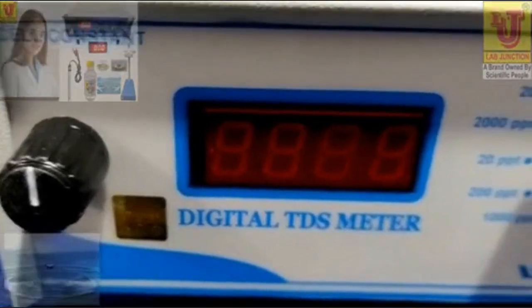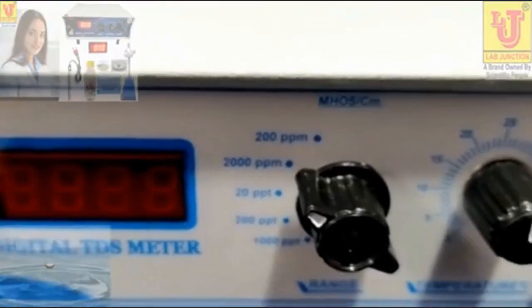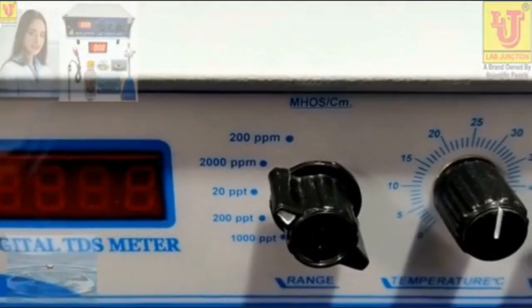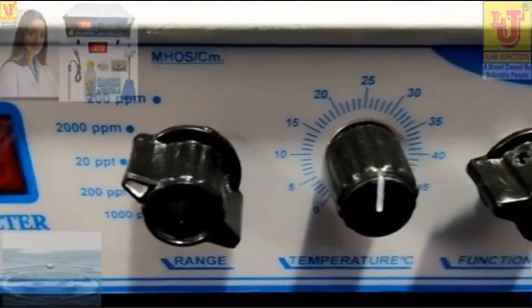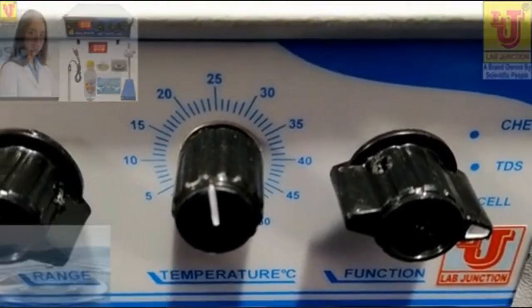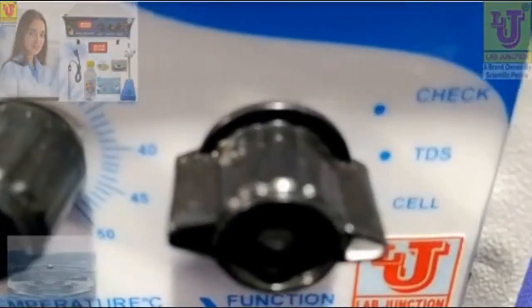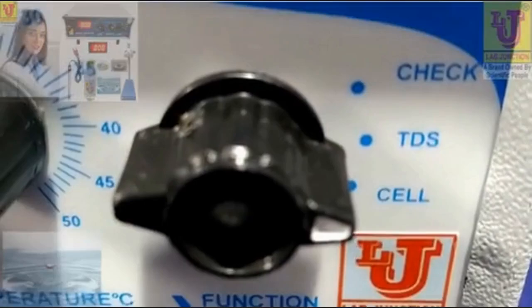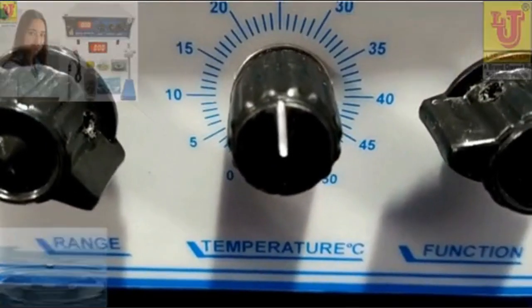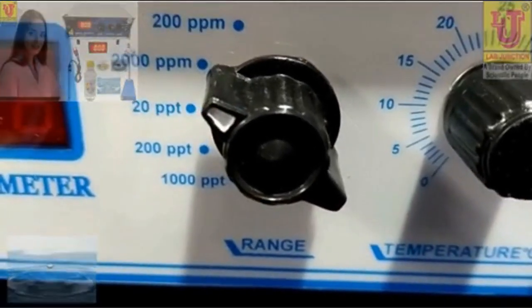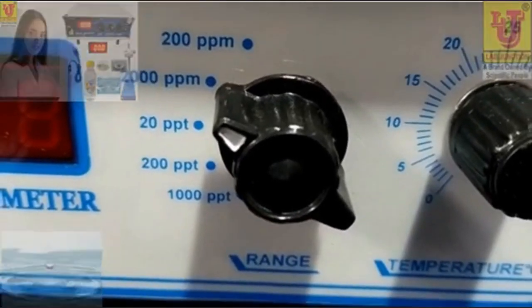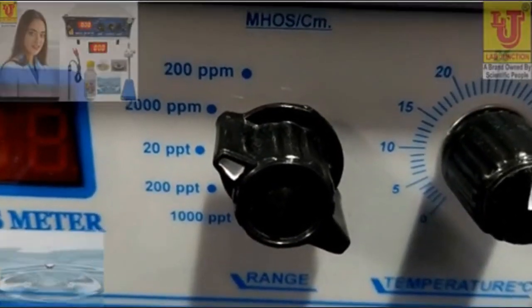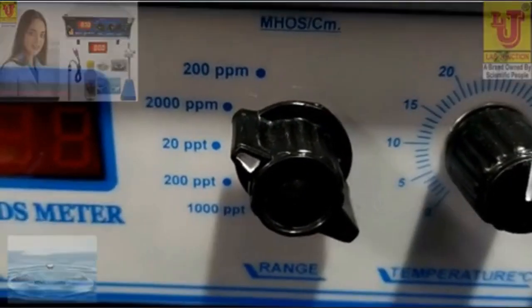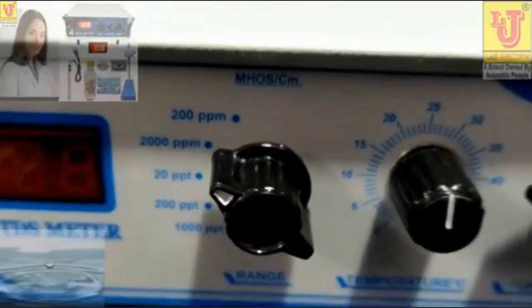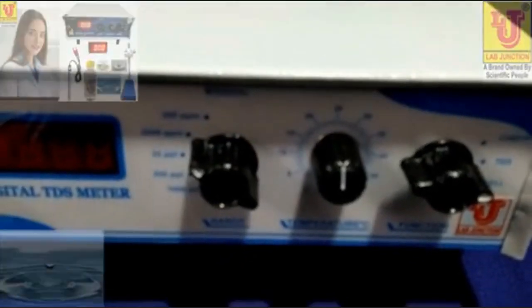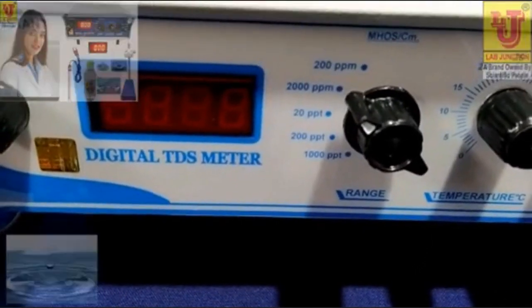front view. In the front view, one is the function control. In this function control, check TDS and cell constant facility. Next is temperature. Third is range. It has ranges 200 ppm, 2000 ppm, 20 ppt, 200 ppt and 1000 ppt. Five ranges are available. Now, last is the cell constant.